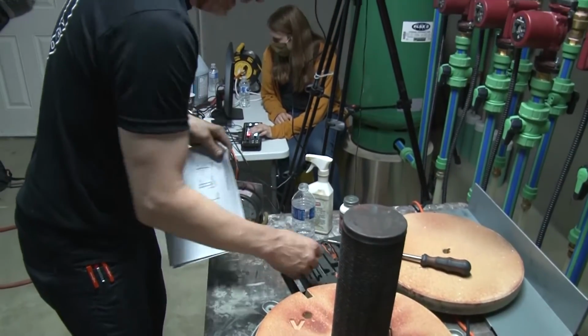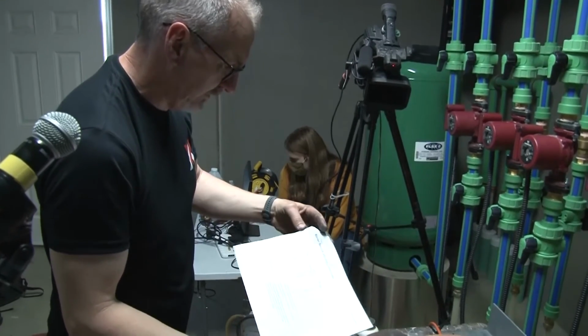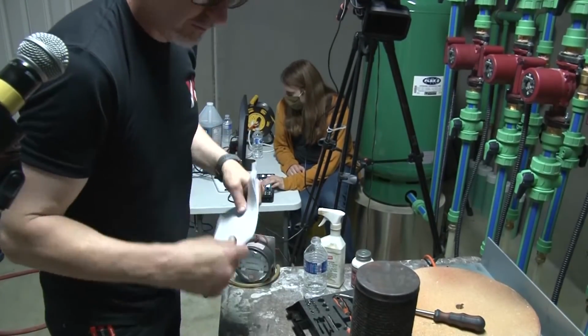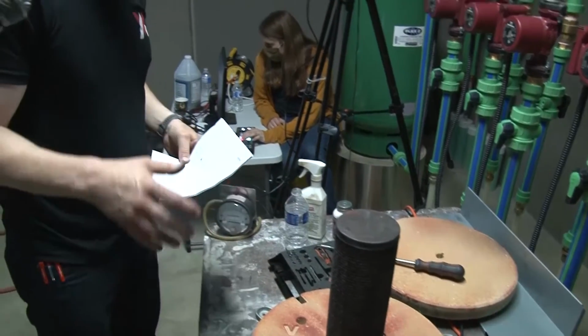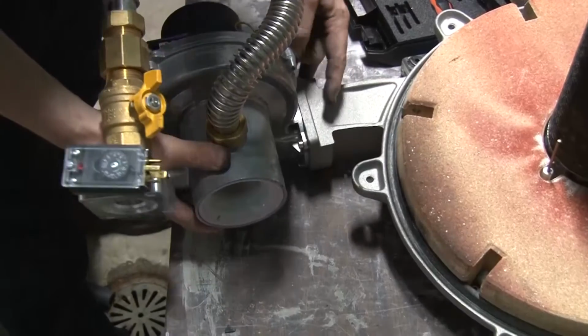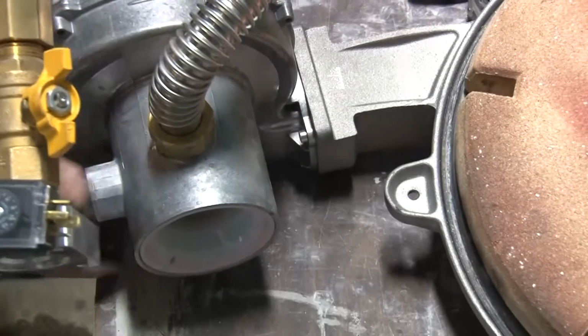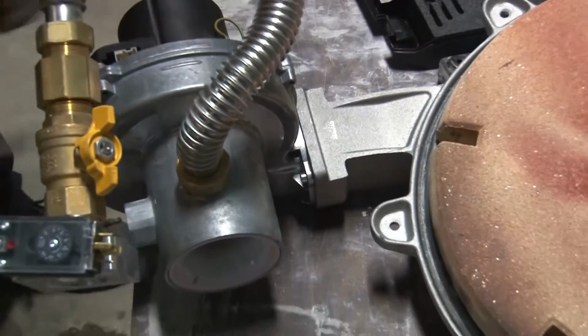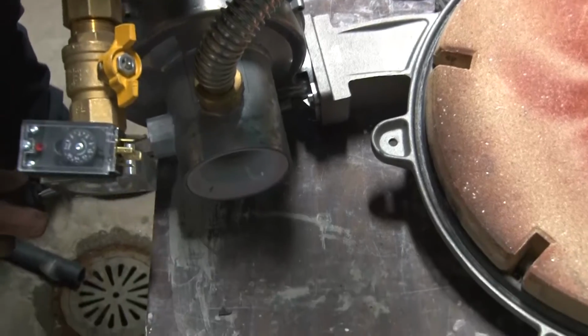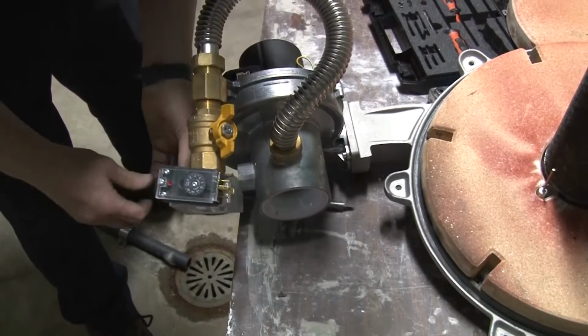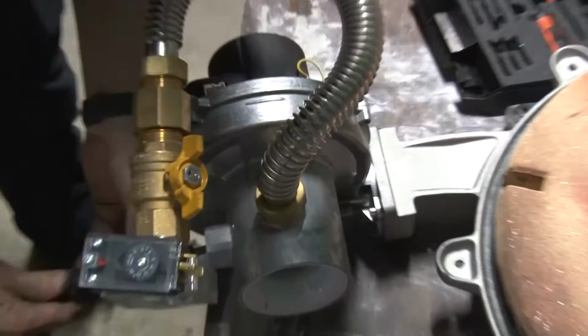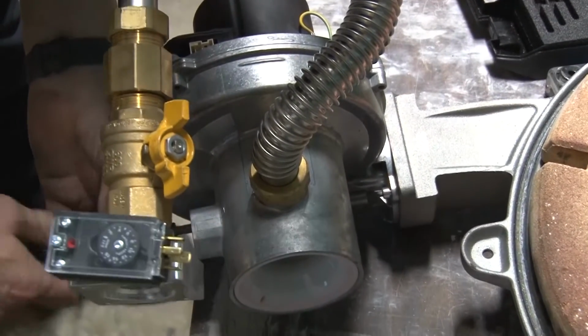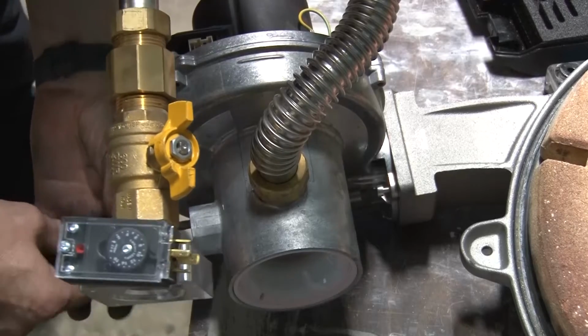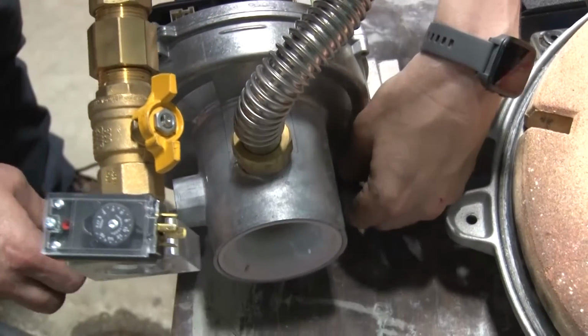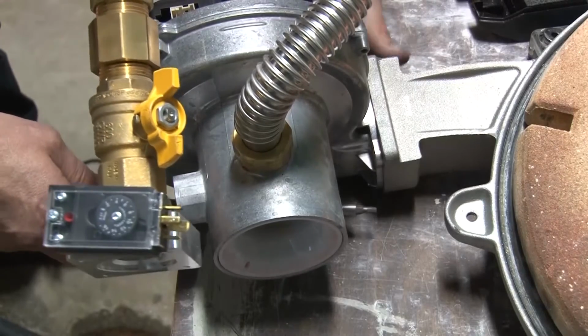Basically make short work of that. And there are tolerances there that you can look at as well to make sure that that's going to be good to go. And the last thing, as far as service goes on these, and inside of here is a little flapper. And the whole idea behind that little flapper is that it basically protects the boiler against negative pressure in your buildings.